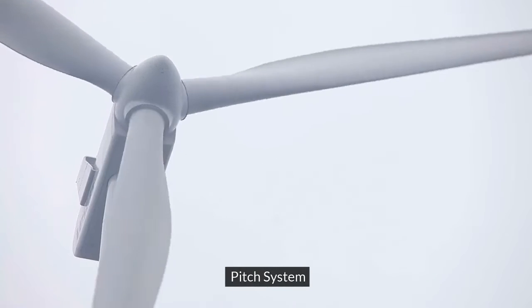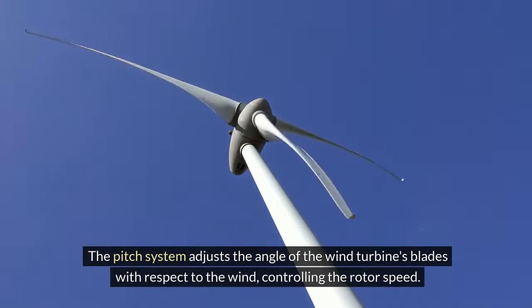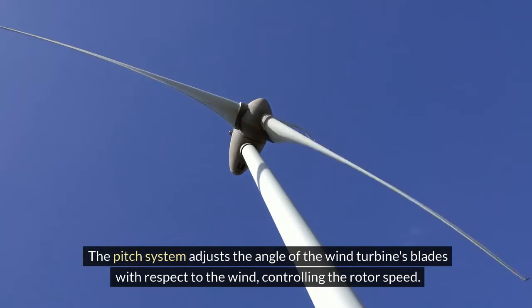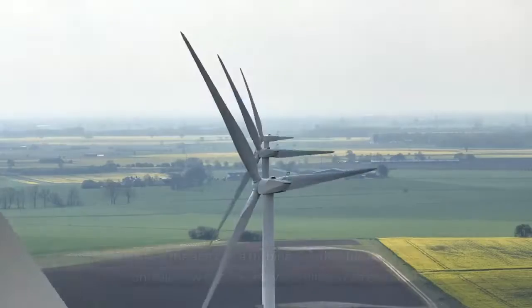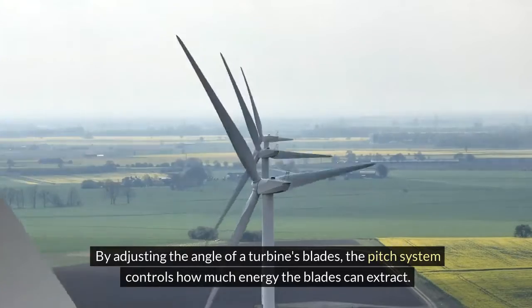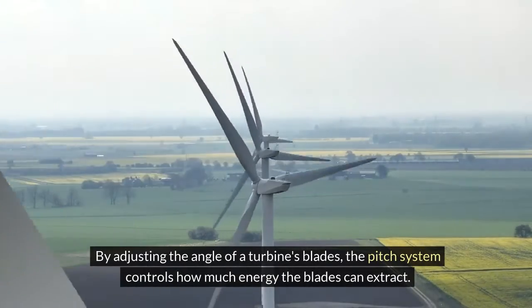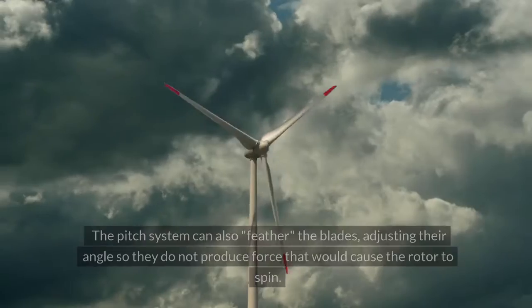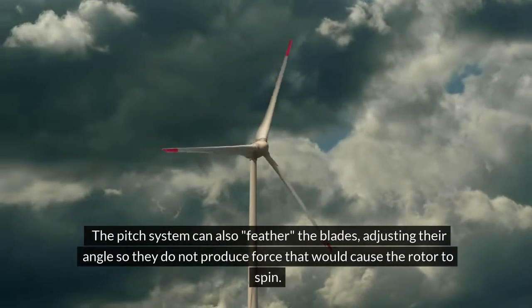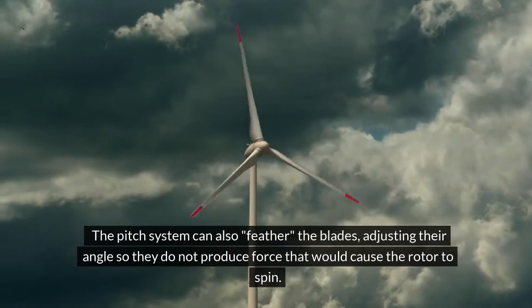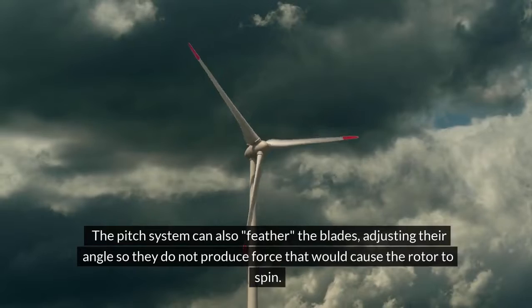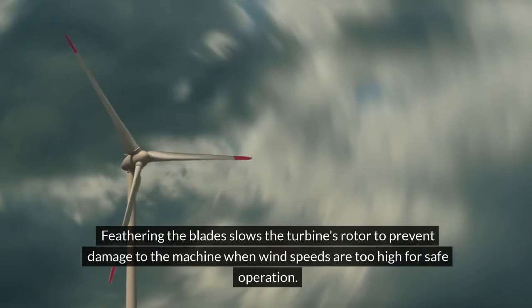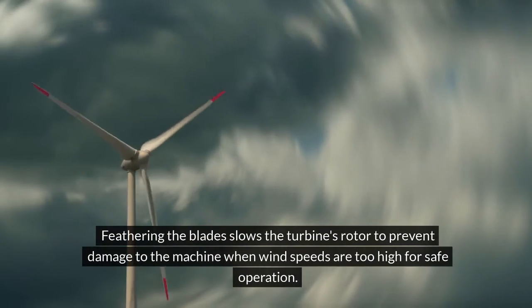Pitch system. The pitch system adjusts the angle of the wind turbine's blades with respect to the wind, controlling the rotor speed. By adjusting the angle of a turbine's blades, the pitch system controls how much energy the blades can extract. The pitch system can also feather the blades, adjusting their angle so they do not produce force that would cause the rotor to spin. Feathering the blades slows the turbine's rotor to prevent damage to the machine when wind speeds are too high for safe operation.